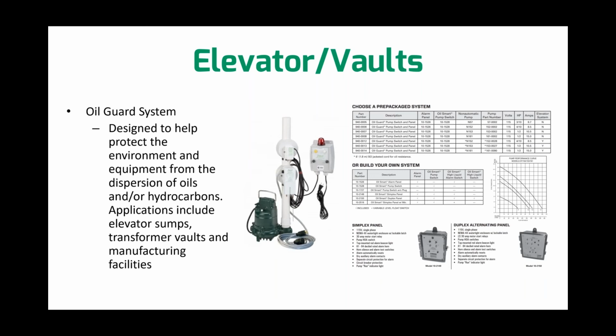Just note that we do have the simplex panel options for one pump and duplex panel options if you're in an application with two pump systems. So the prepackaged system is great, but there are some specifications out there. There are some jobs that are required to have an actual control panel, not just a pump switch and alarm panel, but a control panel. And that's where we offer these both simplex and duplex panels.